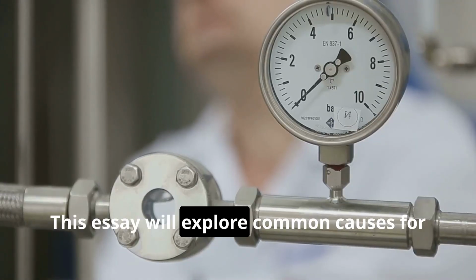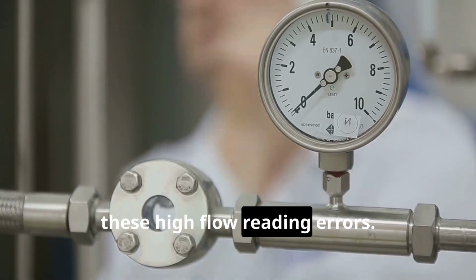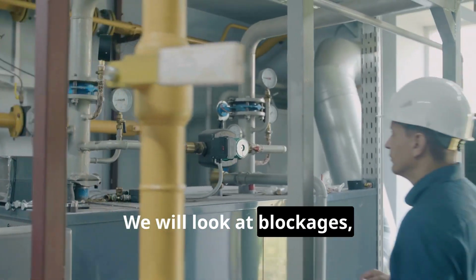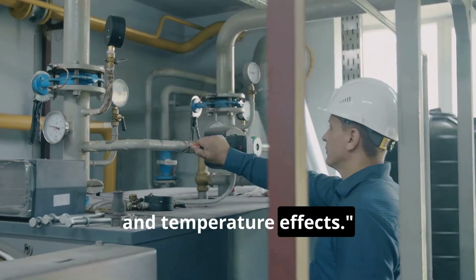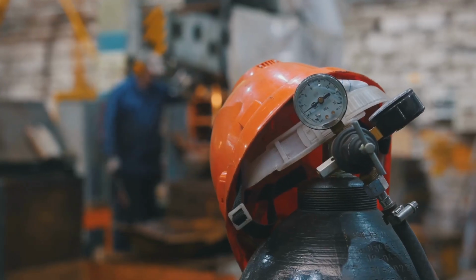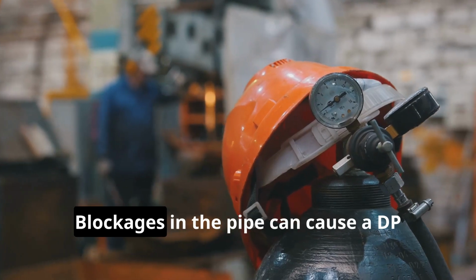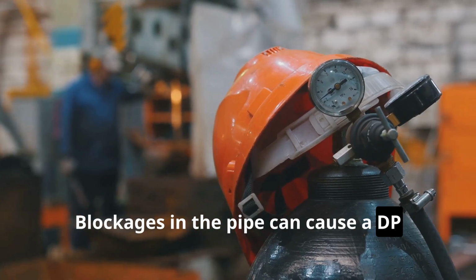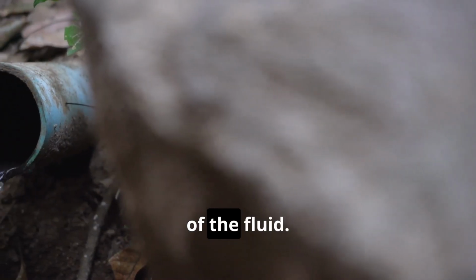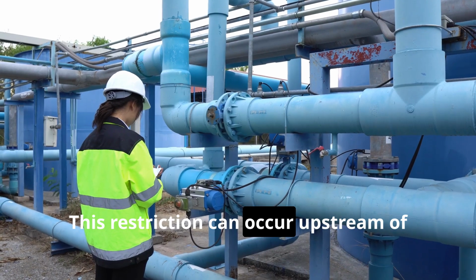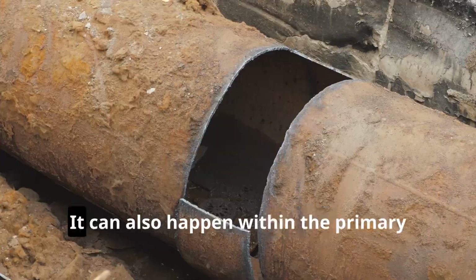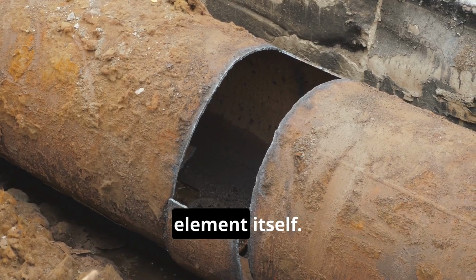This essay will explore common causes for these high flow reading errors. We will look at blockages, calibration issues, and temperature effects. Blockages in the pipe can cause a DP flow meter to read high. A blockage restricts the normal flow path of the fluid. This restriction can occur upstream of the primary element. It can also happen within the primary element itself.